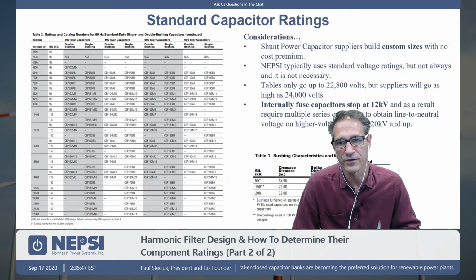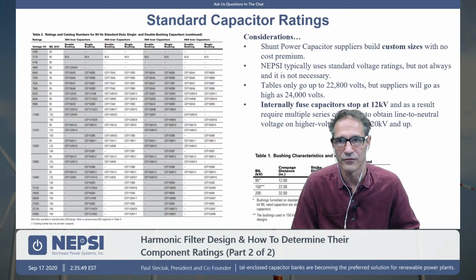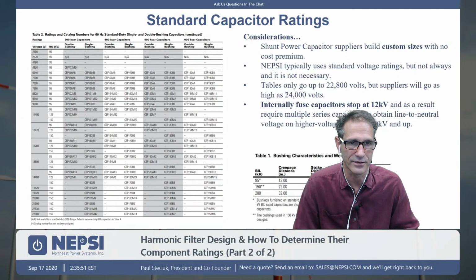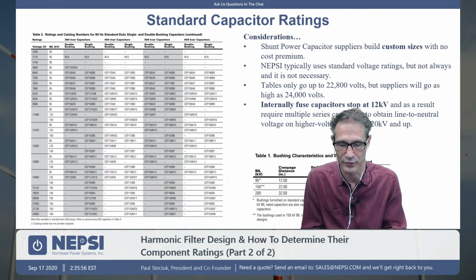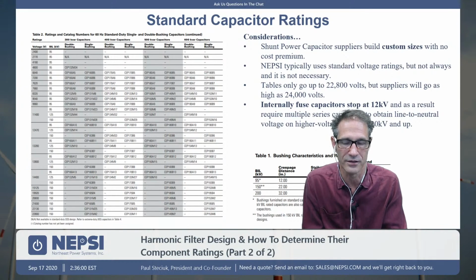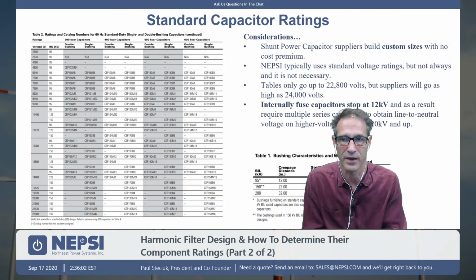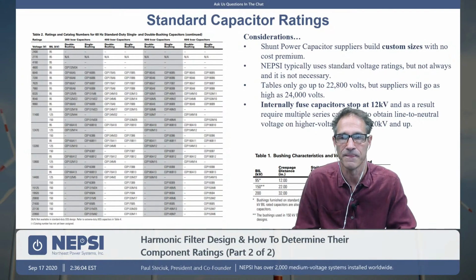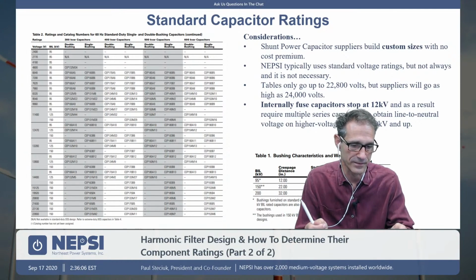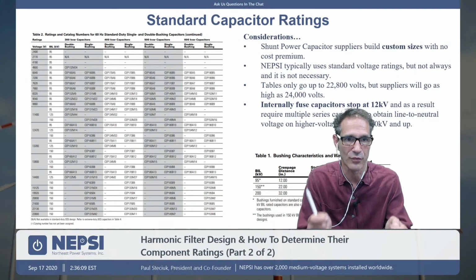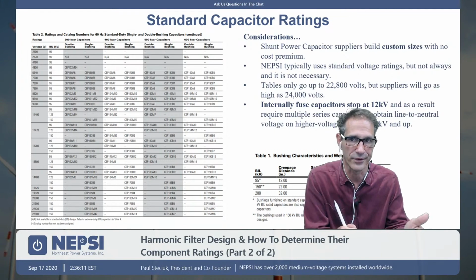You don't pay a significant amount of cost to go from a standard capacitor to a non-standard capacitor. There are no manufacturers out there that we know of that are stocking standard capacitors. So you're not getting any advantage by going with a standard capacitor over a non-standard capacitor. The other thing is the mounting arrangements will change from one capacitor supplier to another.